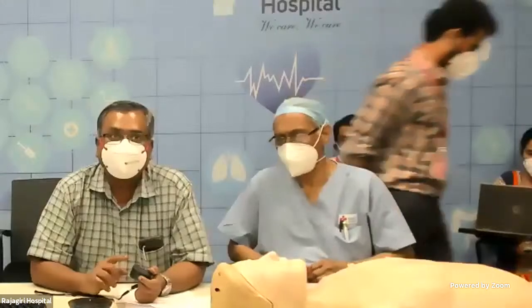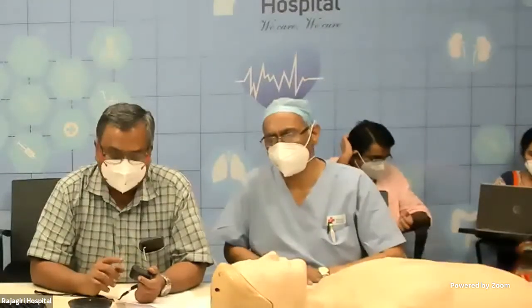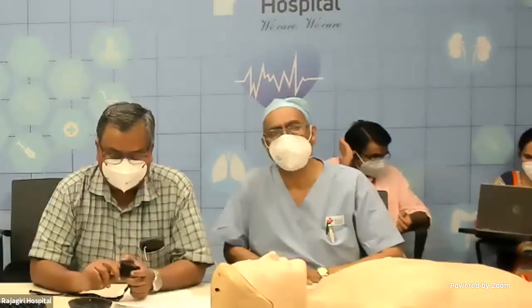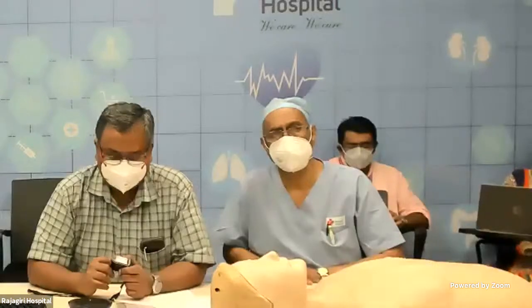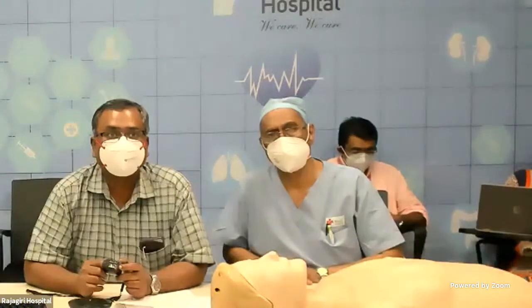So there is certain troubleshooting. One is you can always see a waveform when we switch on the pulse oximeter, along with the pulse, the heartbeats per minute, and the saturation. There is a waveform. If I come closer, the audio will be muted. So any pulse oximeter will show a waveform here. If the waveform is not correct, that means the pulse oximeter reading also may not be correct.